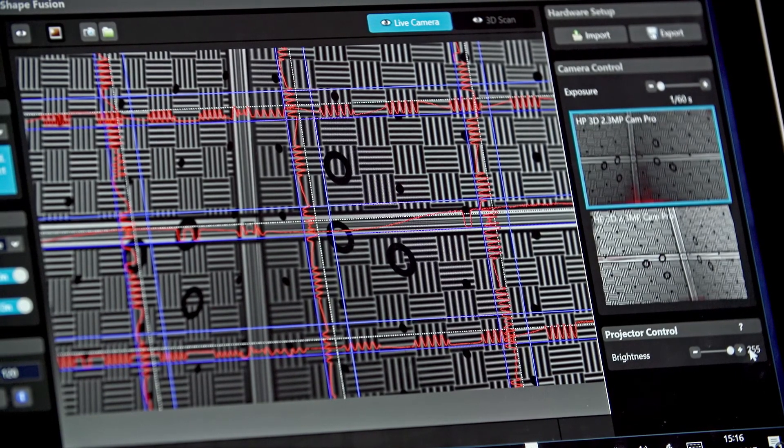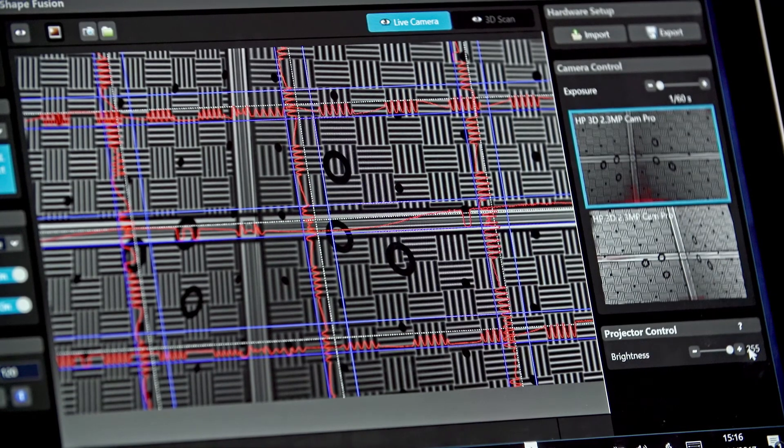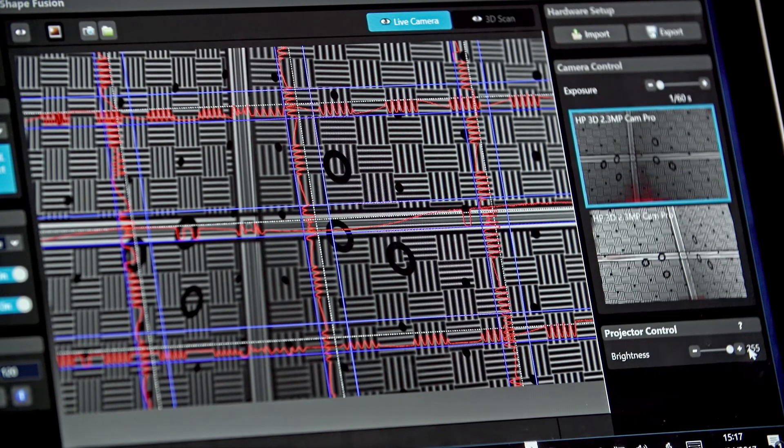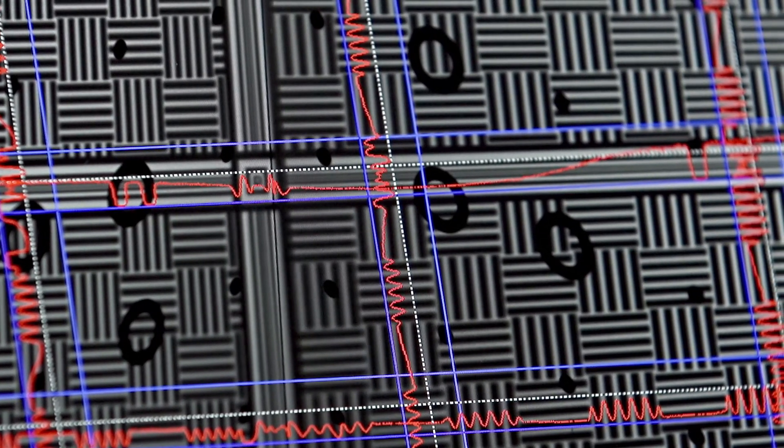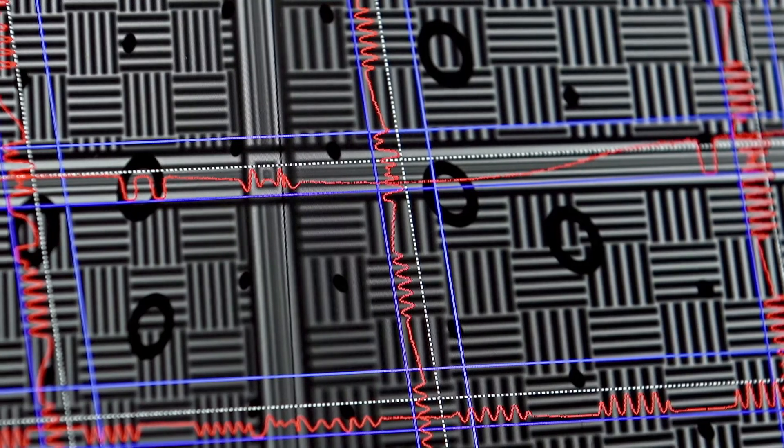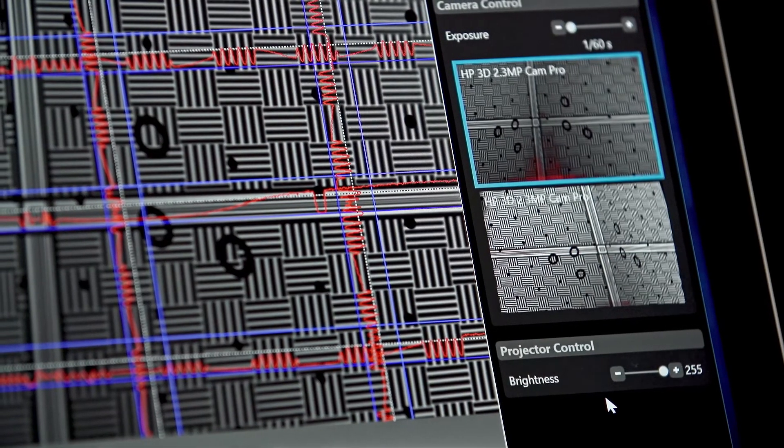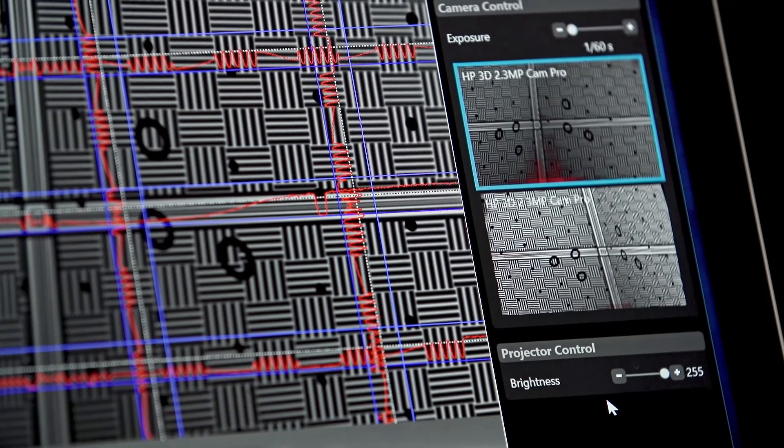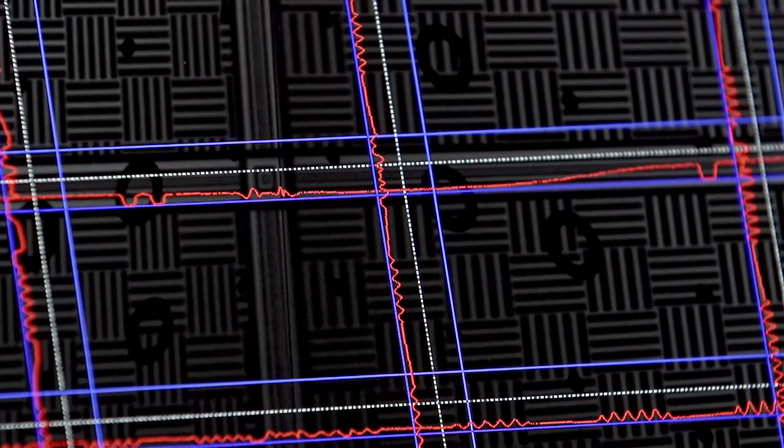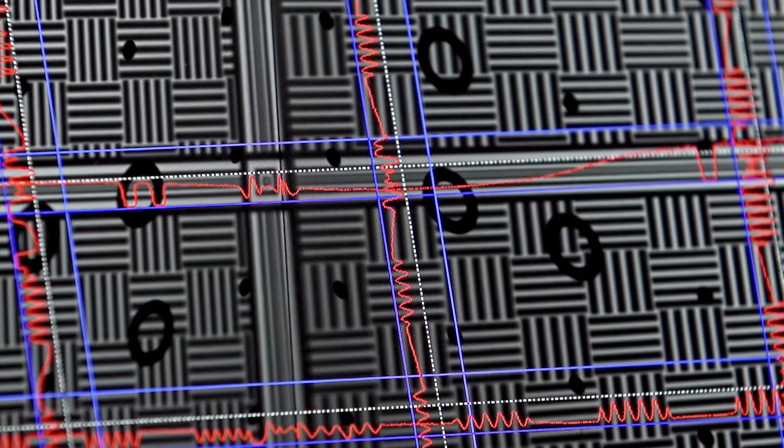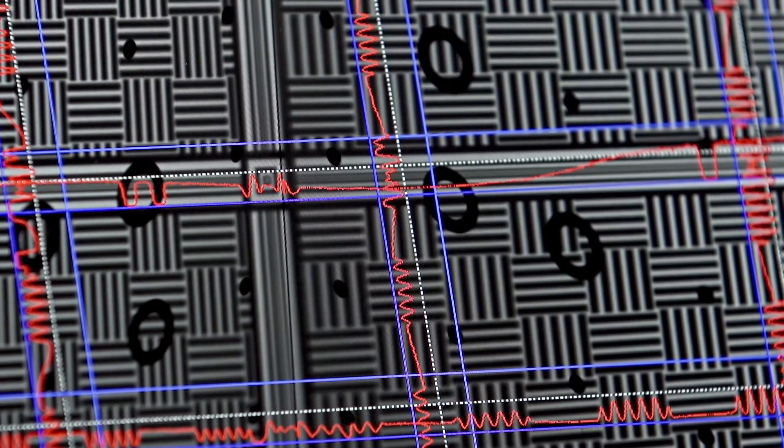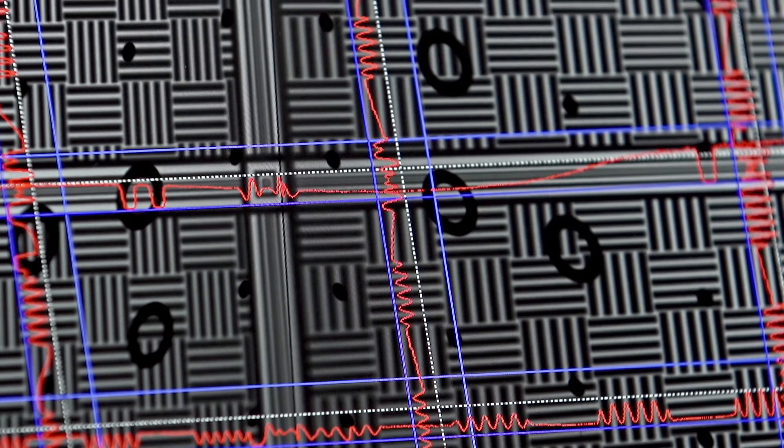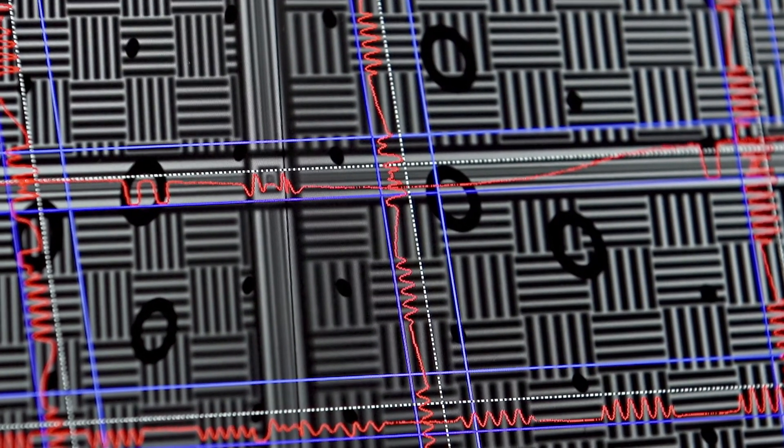Make sure the pattern is visible, clear, and focused. Look at the red intensity sine waves on the image and adjust the brightness slider in the software to assure that the sine waves fit well within the pattern lines. Do not change the mechanical settings on the projector or cameras.